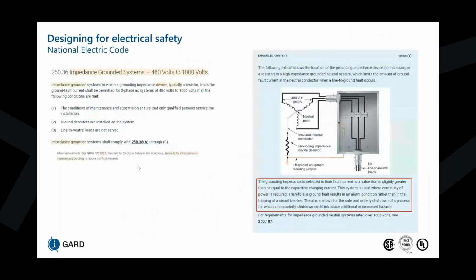Now, in the National Electric Code in 250.36, for impedance grounded systems between 480 to 1000 volts, impedance grounded systems in which a grounding impedance device, typically a resistor, limits ground fault current shall be permitted for 3-phase AC systems between those 2 voltage levels if the following conditions are met. The conditions of maintenance and supervision ensure that only qualified persons service the installation. Ground detectors are installed on the system, and line to neutral loads are not served. So in this case, the National Electrical Code actually prohibits the distribution of the neutral.